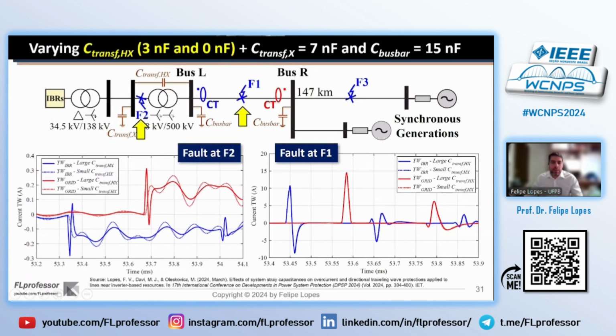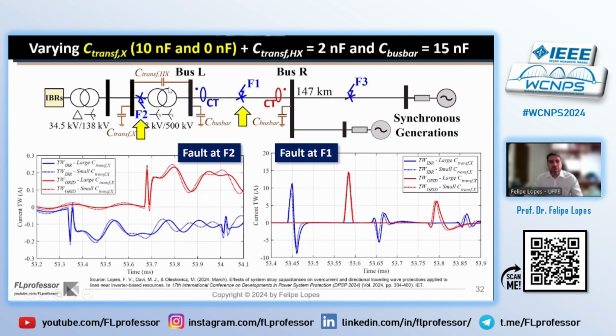Varying the capacitance in between the transformer windings, we can see that it matters more for external faults than for internal faults here. And if we consider the variation of the stray capacitance here on the low voltage side of the transformer, again, we can see some influence and also some reduction of the amplitude here when we change the value of these capacitances.